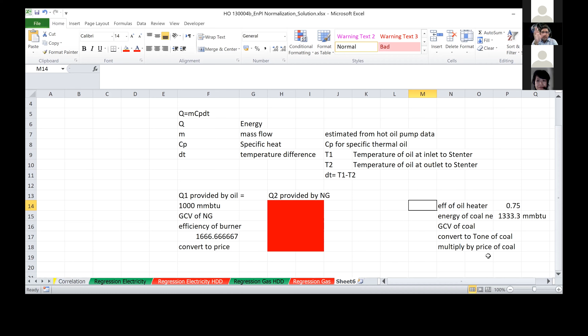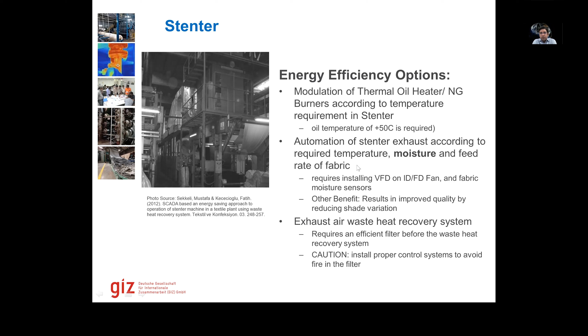So for the stenter, we can have waste heat recovery from air as well. The air that is going out, we can install an air to air or air to water heat exchanger, depending on what is required. Usually I recommend an air to air heat exchanger because it is easier to handle. Installing an air to water heat exchanger is a little bit more tricky, because then you need bigger heat exchangers and you need more piping. If you just install an air preheater, that provides more direct benefit.